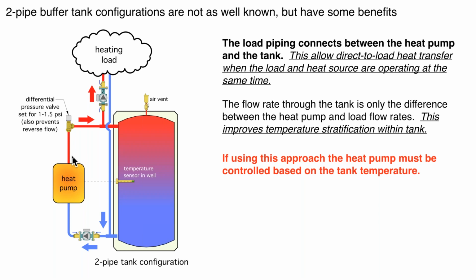But what it does do is it just unnecessarily cools some of that water. You're sending it through piping and through a heat exchanger in a heat pump. And even though that heat exchanger in the heat pump is insulated, that reduces some of that loss, you're going to have some losses there. And so that water is going to cool off a little bit, and then it's going to blend with the tank water, and it's actually going to bring that supply temperature down a little bit. And I will stress, with the heat pump, it's not as much of a factor as it is with a boiler, because a boiler does not have that insulated heat exchanger in it. And you can lose several degrees as that water goes up through there.